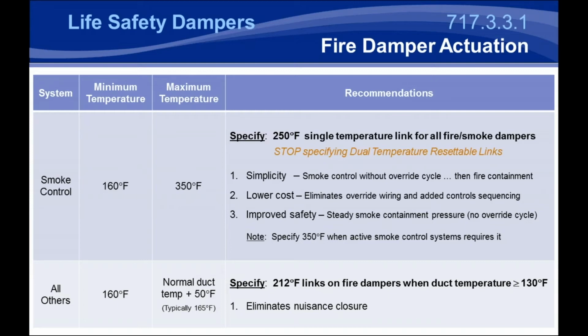The reason for this is there's no need for the override. The damper will stay open for as long as it needs, as long as it's been certified to close. It lowers the cost, so there's less wiring and less controls that are needed, and improves safety by adding that layer of keeping that damper open as long as possible while making sure the damper will close and protect the rated barrier that it's installed in.